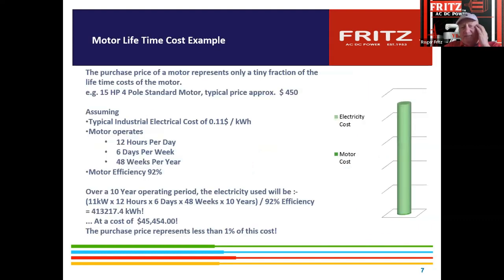This slide's a little bit dated, but take an example of a 15 horsepower motor that cost $450. Now it's almost $750, $800. If it ran 12 hours a day, 6 days a week, 48 weeks a year, back at 11 cents a kilowatt-hour, and a lot of times we're now sitting at almost 22 cents, over 10 years the motor utilized $45,000 worth of power. Now it's more around 70 or 80,000.